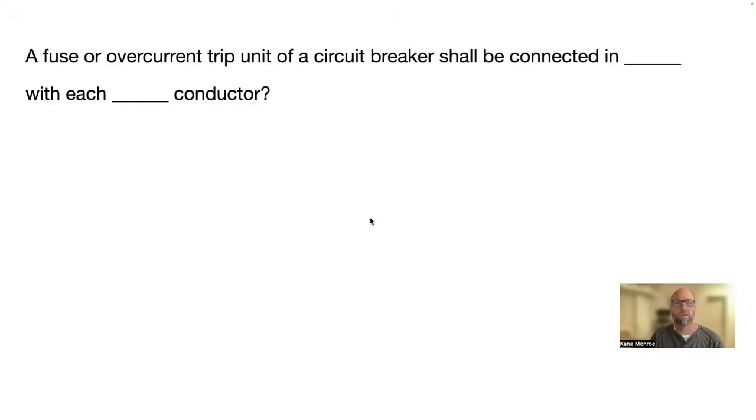A fuse or overcurrent trip unit of a circuit breaker shall be connected in blank with each blank conductor. Guys, this is a common question, a very common question here. So it should be connected in series and it should be connected to the ungrounded conductor. So series and ungrounded. Because if it was parallel, then remember, your voltage could go around. Series, it has to stop right there.